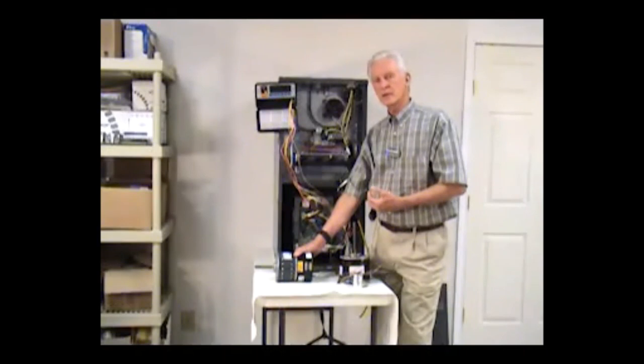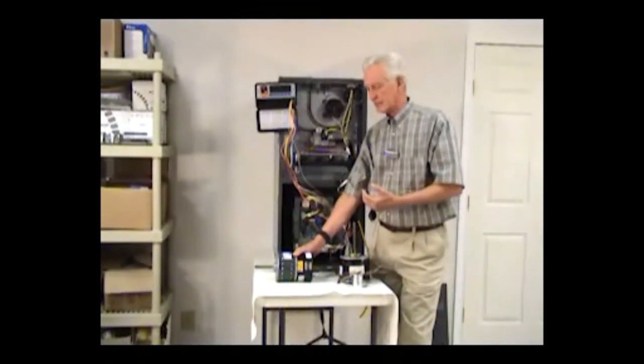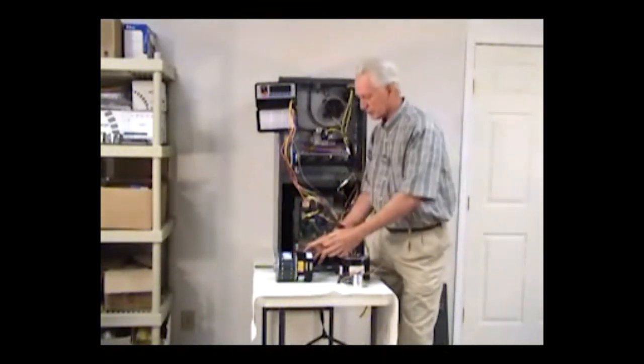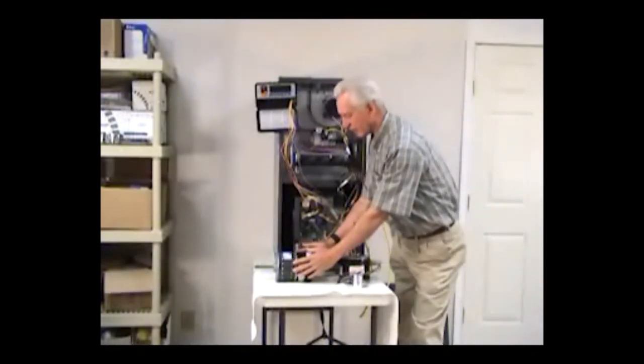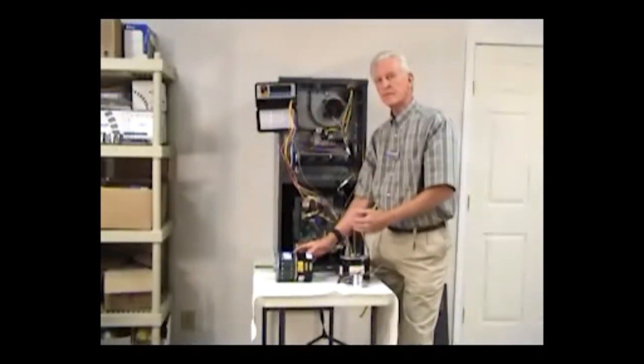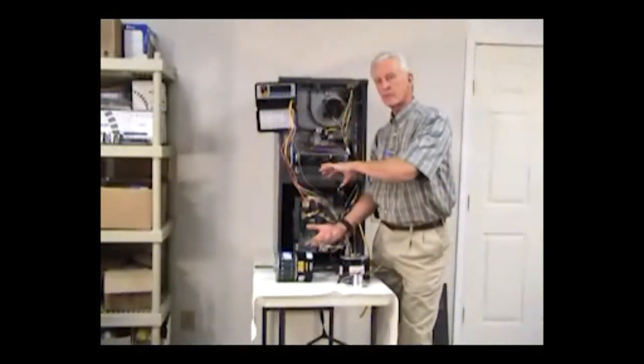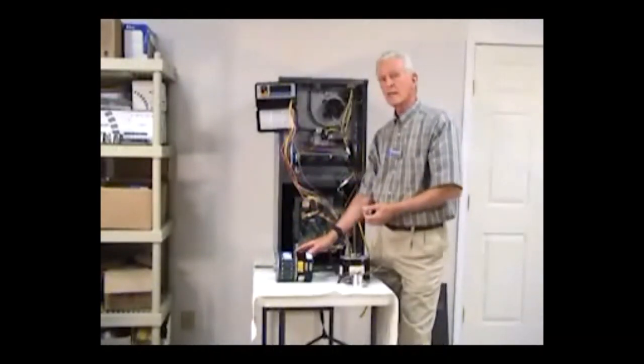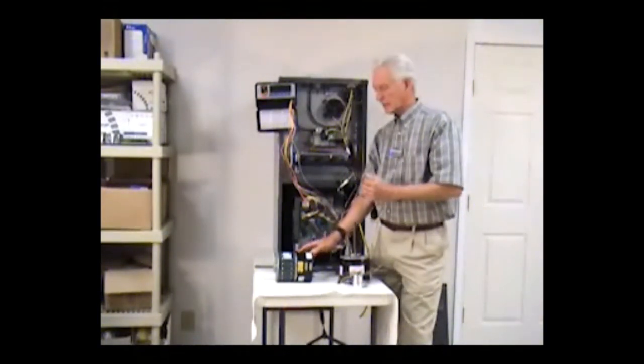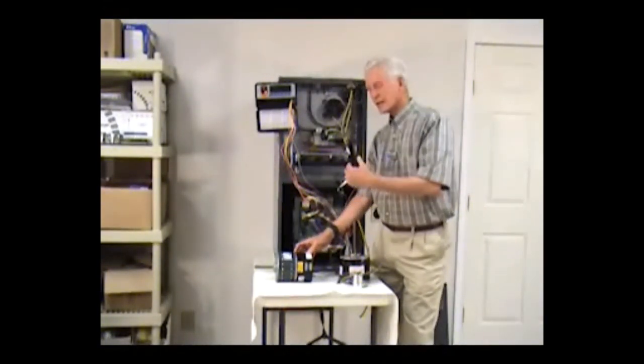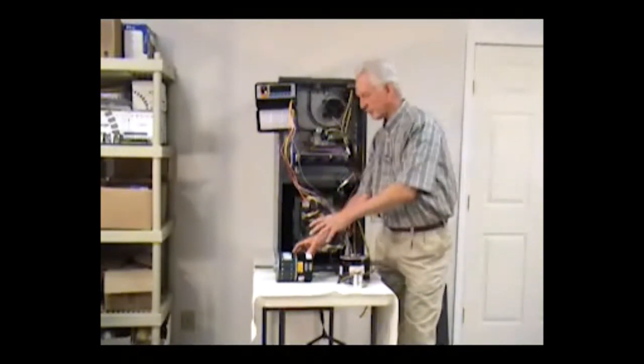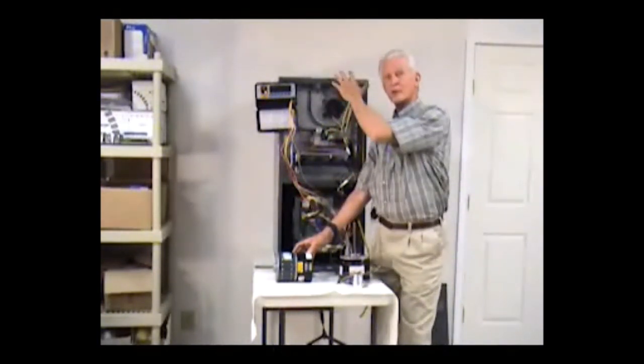If you are removing a motor and reinstalling it, it is highly recommended that you reinstall the motor back in its original position that the manufacturer has it in there. Don't rotate it around or put it in a different position than what you took it out. If you do, then you could possibly run into water problems. The other situation is condensation problems don't always develop in here. Sometimes they develop up on top.